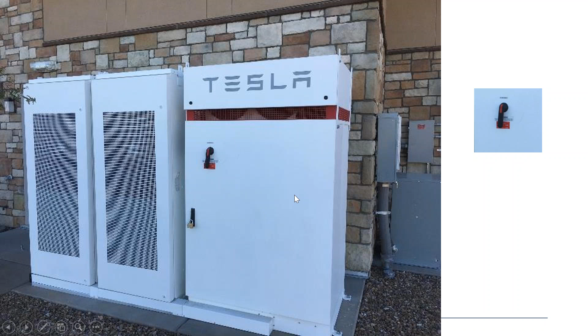And then you also have the connection to the other energy sources. If we remember earlier, I was talking about how you have to have some other type of energy source. Under the connection to those other energy sources, you can have loss of interactive system power. Upon loss of a primary source, an energy storage system with a utility interactive inverter shall comply with these requirements. What this allows you to do is it tells you how to do the installation so that when you lose your utility power, your energy storage system now takes over that responsibility.